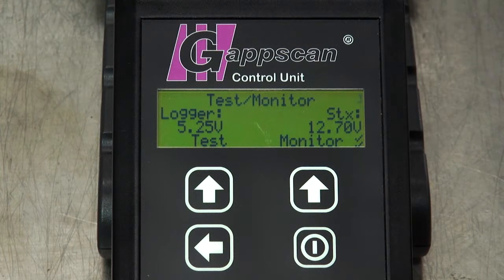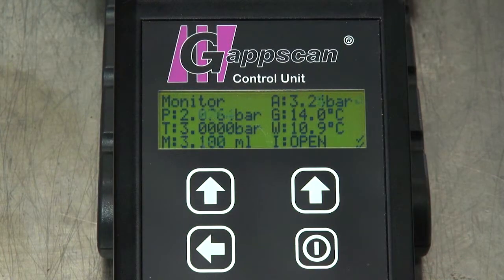Select Mon Test and then Monitor for the monitor mode. This allows you to monitor the test parameter and see when stabilization has occurred and the test is ready to start. This is an example of the screen that you will view in monitor mode as the pressure is stabilizing prior to running the test. Starting from the top left, the screen shows P, which is the pressure of the closed circuit, T, the target pressure, usually set to 3 or 5 bar, M, which is measured flow over the test period, A, pressure of an internal vessel within the Gappscan unit. This needs to be higher than the highest pressure from P or T to balance the pressure between inlet and outlet.